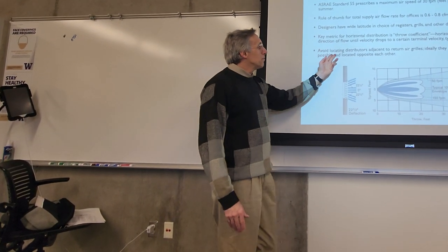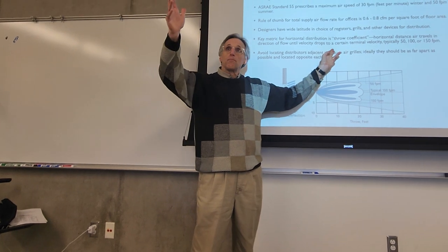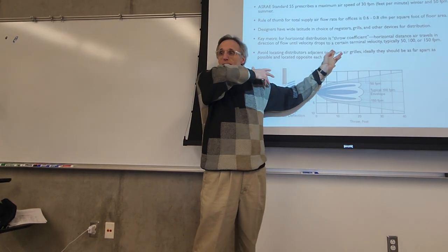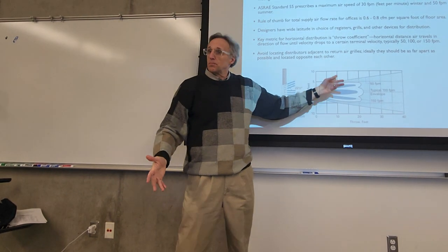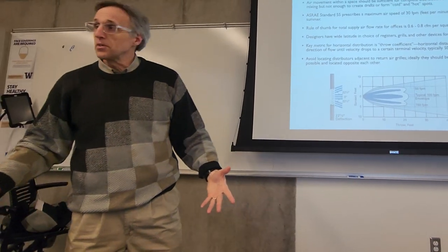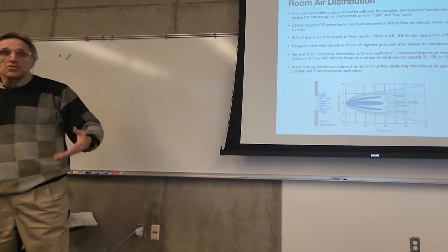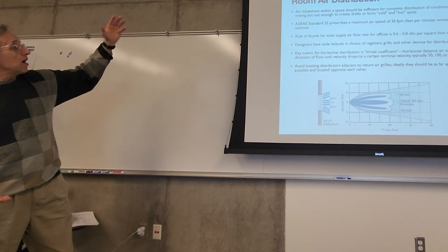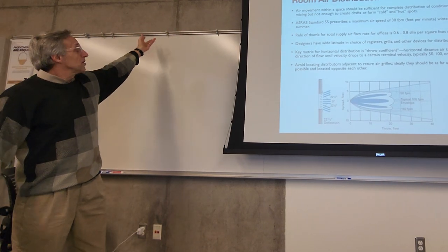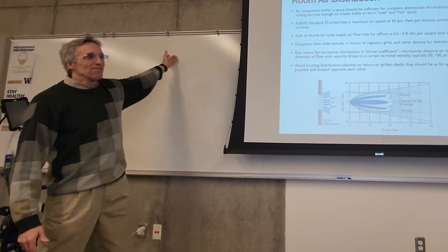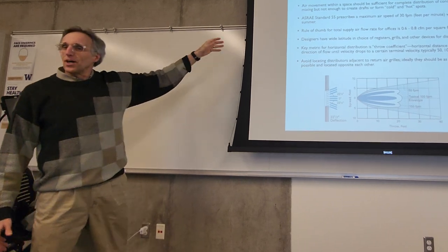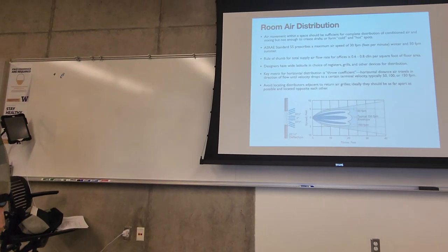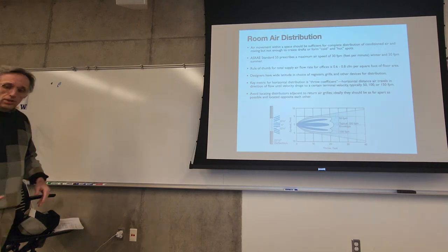You don't want your registers pushing the air out right beside the return air, okay? This happens. I mean, this happens. Experienced engineers design a system, you've got the air coming out, and then the return air is right beside it, so the air comes out and it goes right back in. It comes out, shoo. It's like, whoops, somebody messed that up. You don't want to do that.